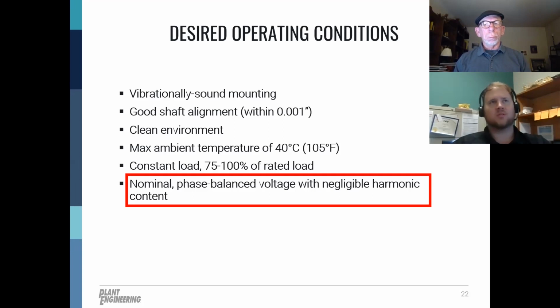So, what is the difference between the motor nameplate and what the utility is supplying? That 10, 20, 25 volt difference accounts for voltage drop in your distribution lines to your facility and then also within your facility. Slight overvoltage is actually all right, but what you really don't want to have is undervoltage at your motors. If you have a multimeter, you're checking voltage at the motor terminals and see some voltage under the nameplate rating, you should probably troubleshoot that and try to determine the cause. We'll come back to some of these voltage issues a little bit later on.